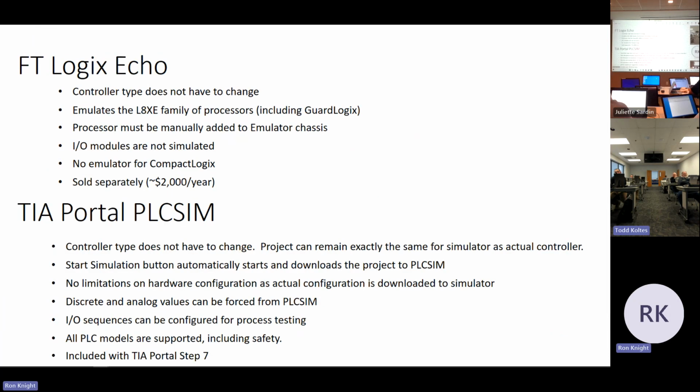So Echo is a little bit better than Emulate. The controller type doesn't have to change. It does all the L8 family, including GuardLogix. You still have to do some manual configuration. It doesn't simulate I/O, and there's still no emulator for our CompactLogix. Again, same bullet points for PLC Sim.